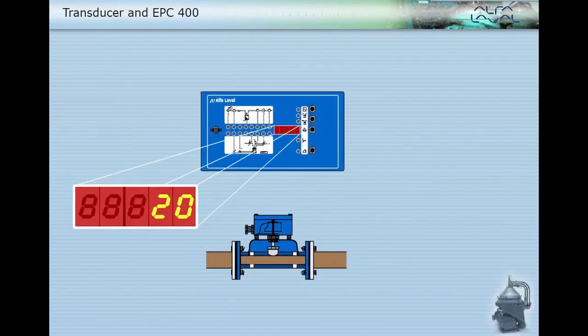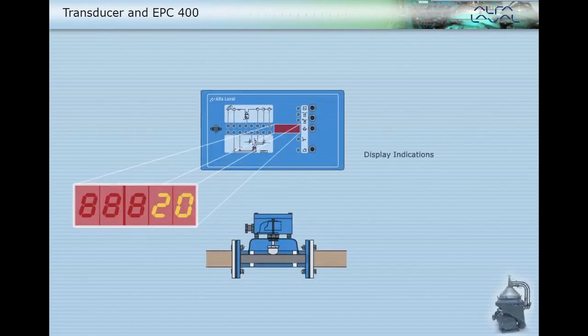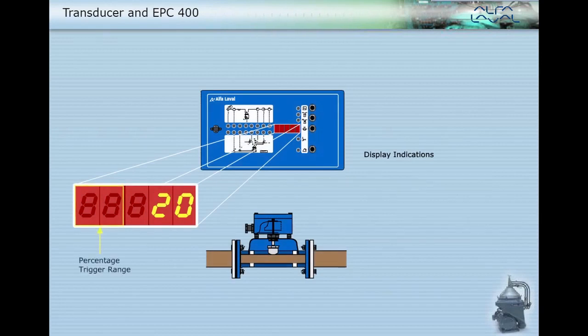Let's now look at how what is happening inside the transducer is indicated in the EPC 400 display. The left-hand side of the display is an indication of the change of the amount of water in the oil. This is called the percentage trigger range. The right-hand side of the display indicates the time to the next timed discharge.